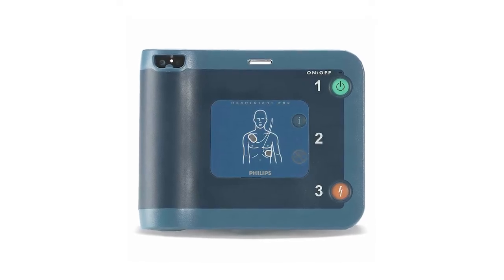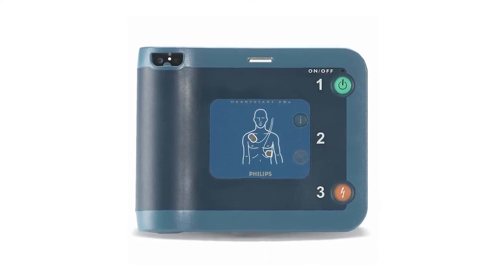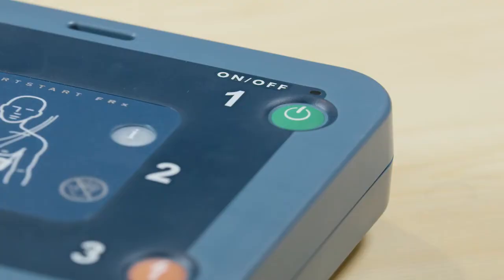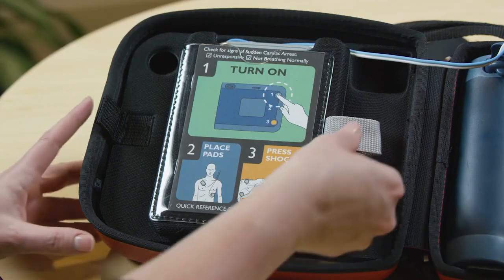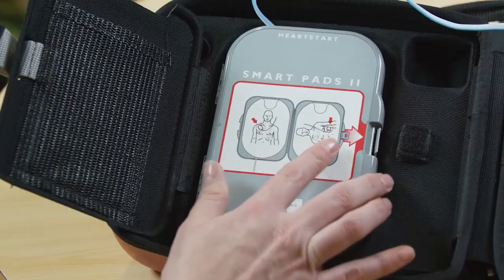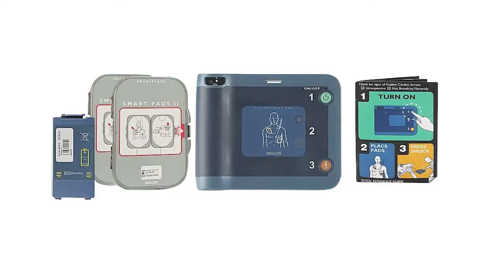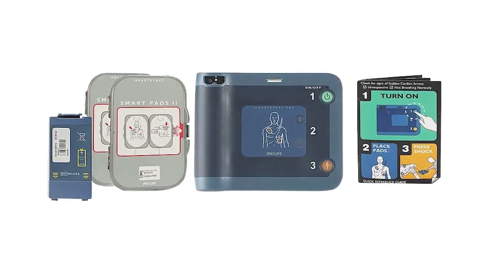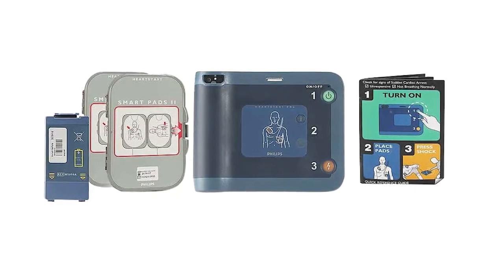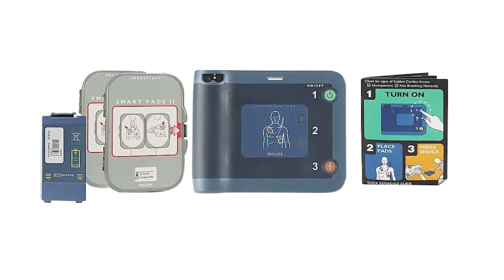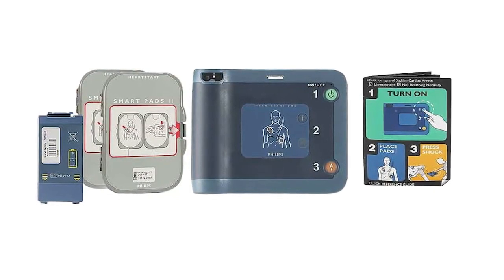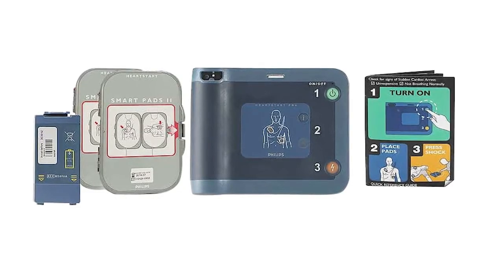Periodic maintenance of the HeartStart FRx is minimal, but be sure to regularly check that the green ready light is blinking. Check any spare accessories for damage and replace any that are expired. Inspect the outer casing of the unit for cracks or damage. If damage is present, contact Philips technical support for assistance. All regular maintenance checks should be recorded in the inspection log.